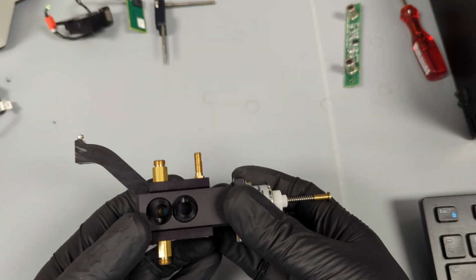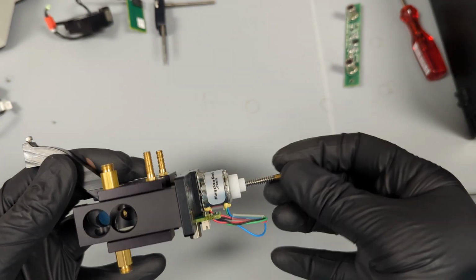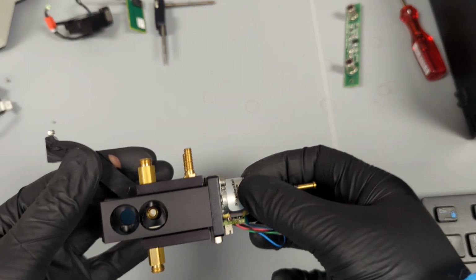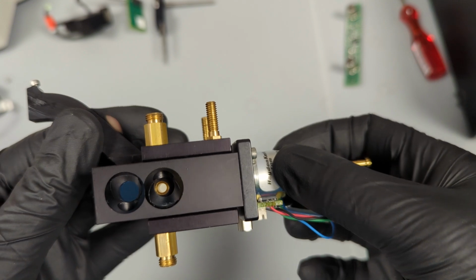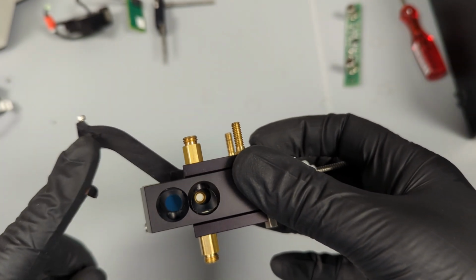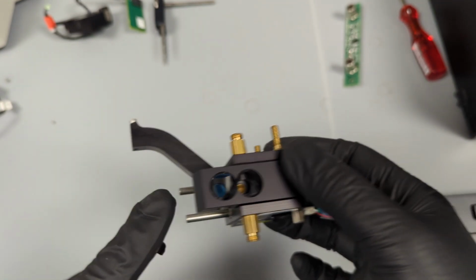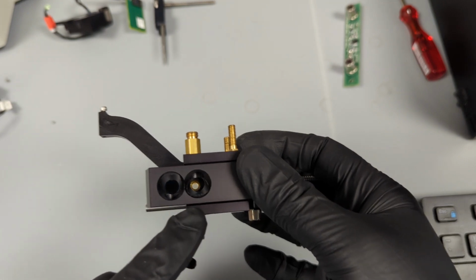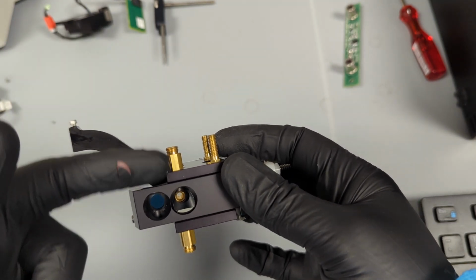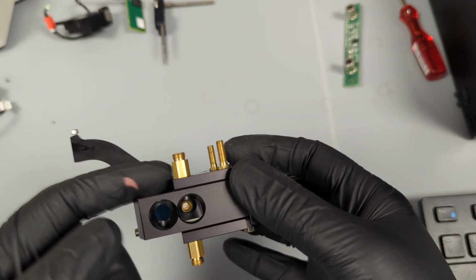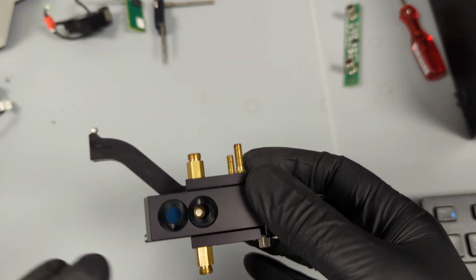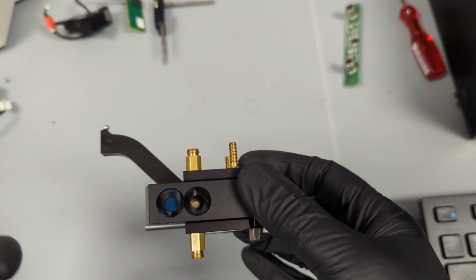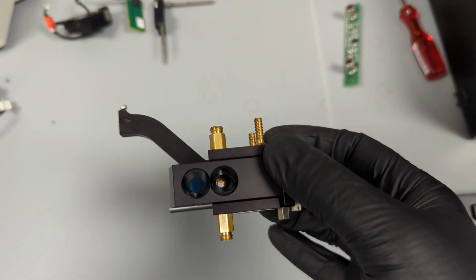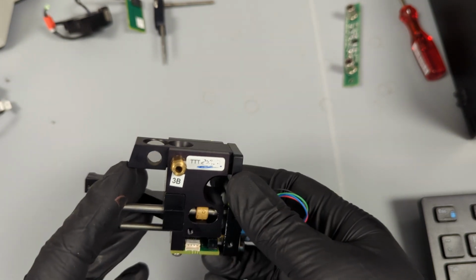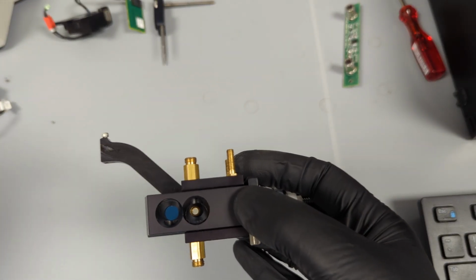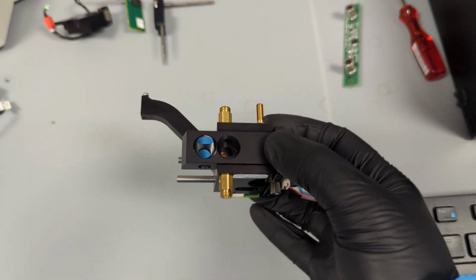And then as it moves here, there you go, you've got another set of mirrors. You can see directly down into it, which allows the light to pass through this tube here, and it will end up coming out here, and we'll get to where that goes in a sec. But there's also a mirror that is directing the light through this optic cable here, 3A, and I believe this is also the absorbance optic cable. On this instrument, absorbance is read from the bottom at the bottom read head as well, so it's reading from the bottom and not the top. So this selector is allowing you to choose between top reads, absorbance reads from the bottom, and then also bottom reads that you can do with fluorescence and luminescence as well.